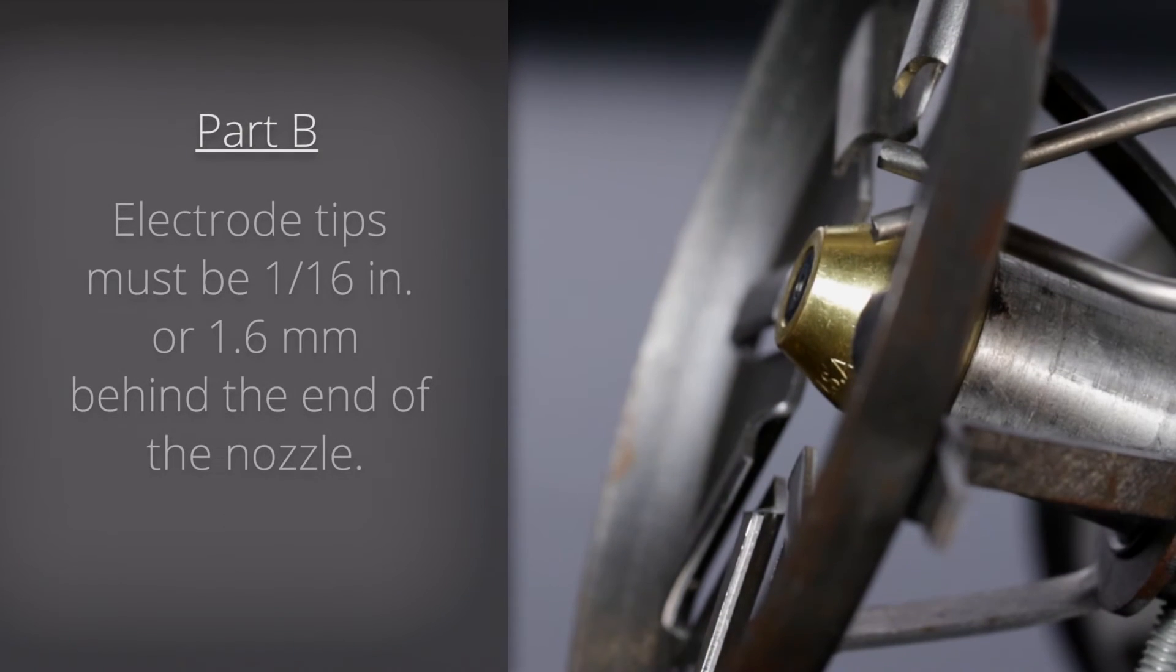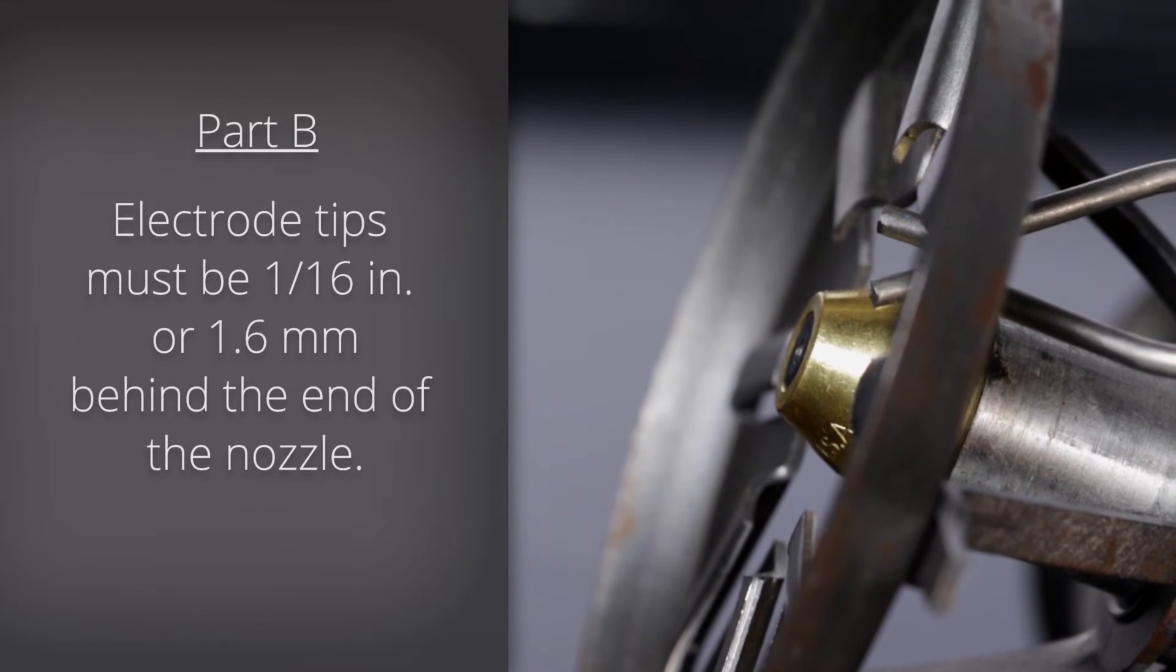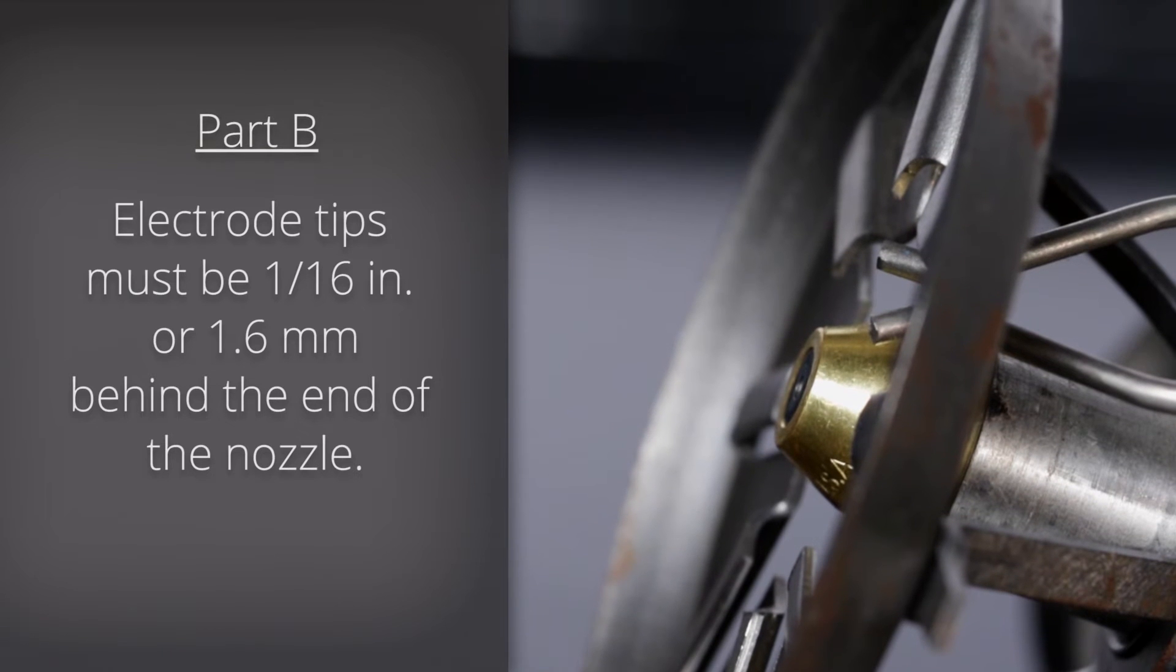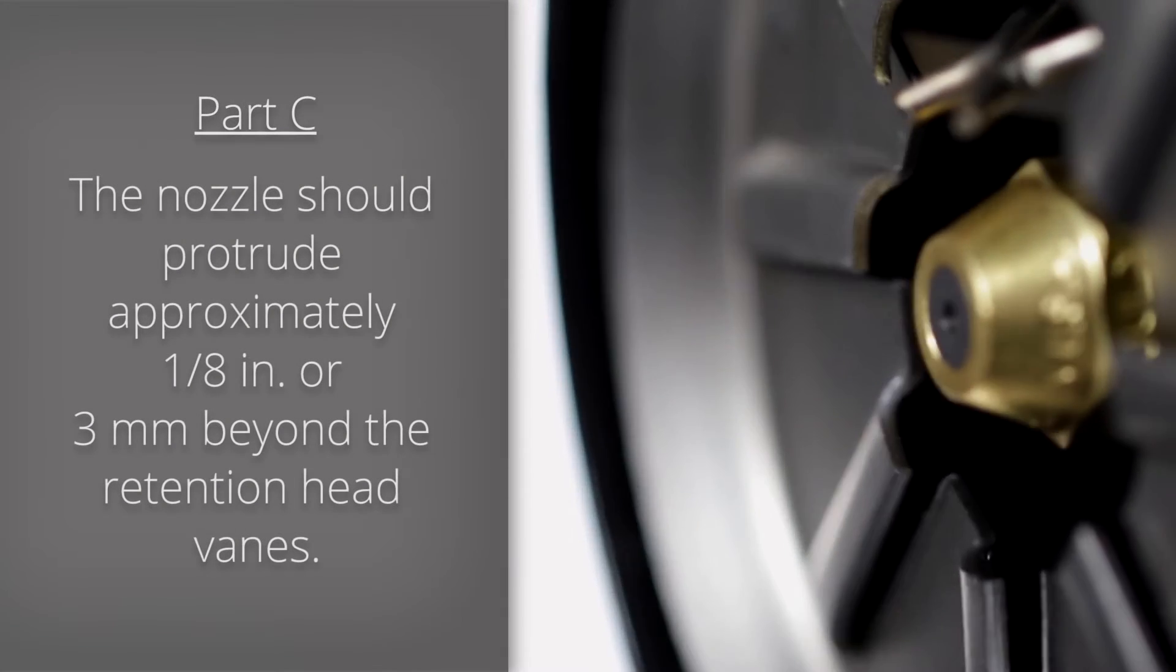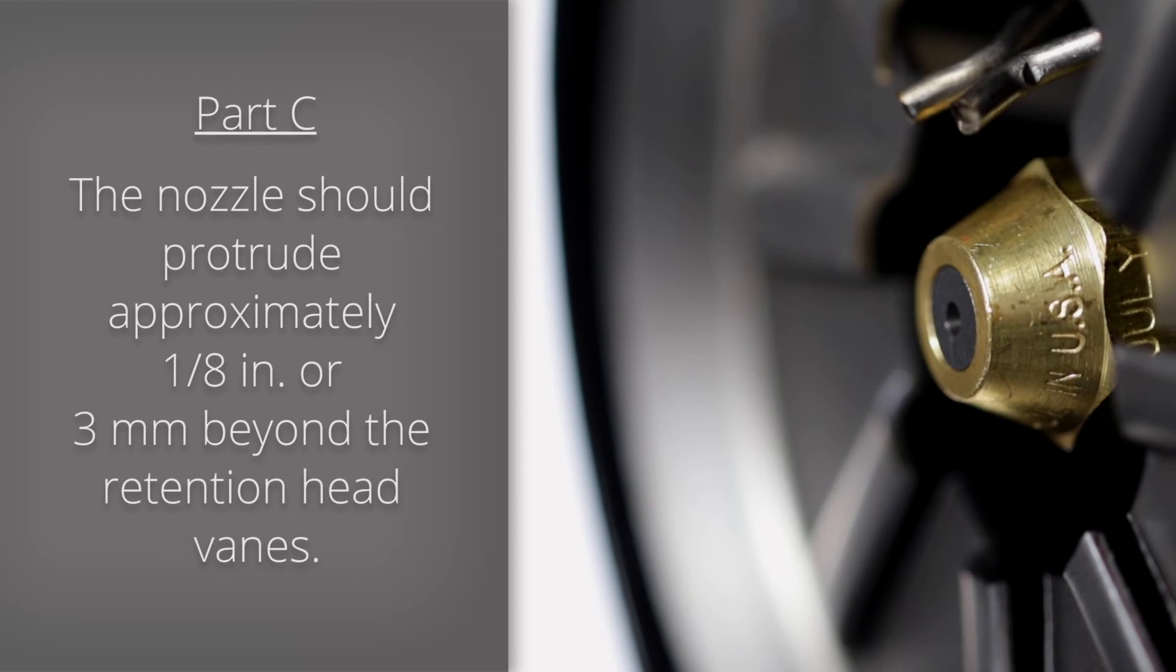Part B: Electrode tips must be 1/16th of an inch or 1.6 mm behind the end of the nozzle. Part C: The nozzle should protrude approximately 1/8th of an inch or 3 mm beyond the retention head vanes.